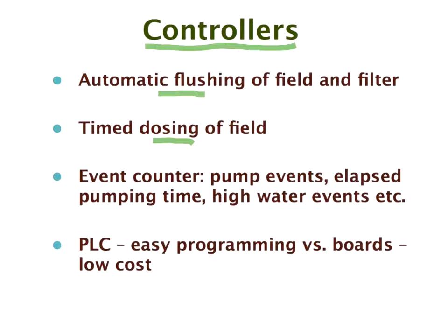Controllers vary. There are PLCs, programmable logic controllers, that are easy to program, can store a lot of data, and can be connected up to telephone lines or to wireless services to send out information automatically. The alternative, at the bottom end, is boards. Boards are much lower in cost, but they don't have that versatility.